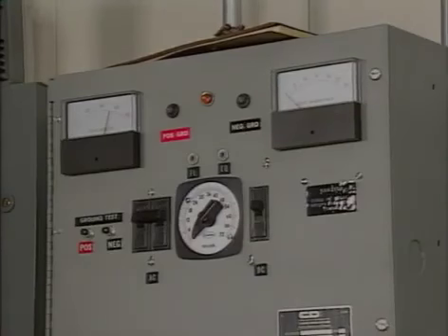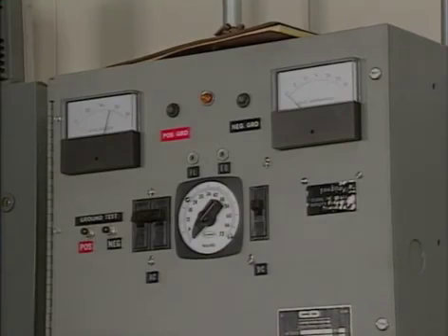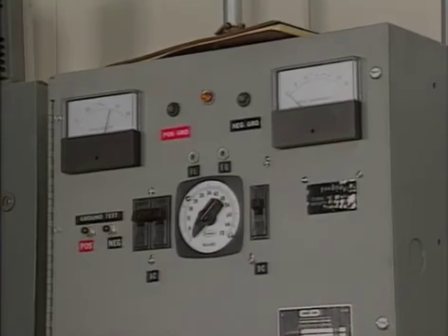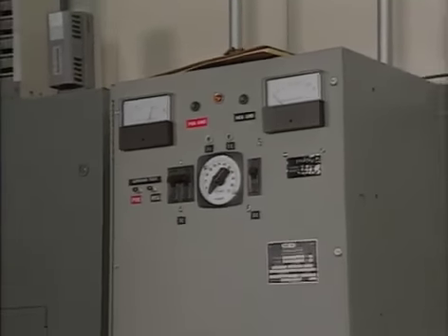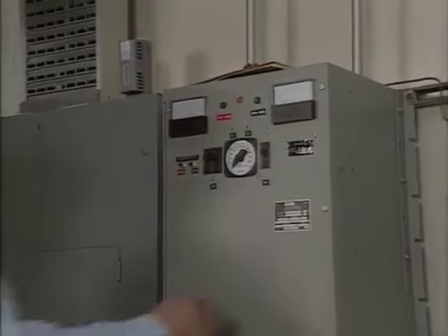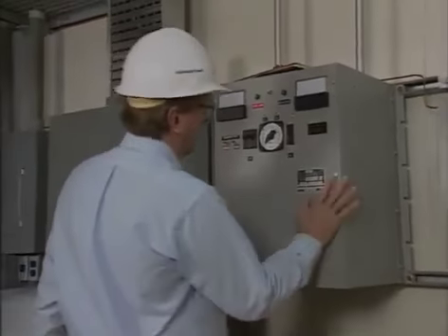Routine charger inspections and adjustments are typically done while the charger remains in service, so internal terminals will be energized. As usual, all required safety precautions should be observed. In general, charger inspection and adjustment steps can be done in any sequence.